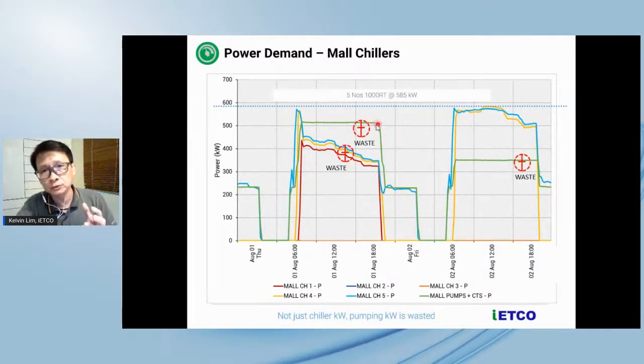It's not just energy wasted on the chiller, but also on the pumping power. When 2 chillers are running, the pumping power is at this level. When 3 chillers are running, the pumping energy is at this level. Imagine when chillers run for about 8 to 10 hours a day, that's a lot of energy being wasted.